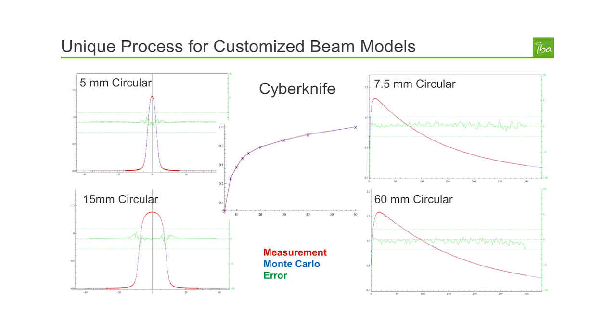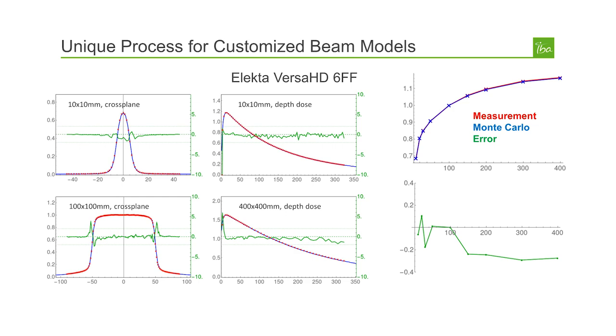The image in the center is the output factor curve for the CyberKnife beam, and again we achieve an output factor accuracy of less than 0.5% for the CyberKnife. In the left-hand column we see two cross profiles for circular collimators of the CyberKnife with a 5 mm and a 15 mm circular collimator. The same level of accuracy can be achieved for accelerators with a large field.